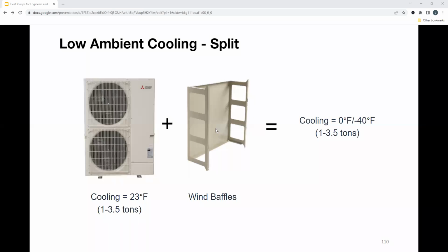And then quickly I just want to mention, I know Alex talked about this a little bit, the difference between low ambient cooling and low ambient heating. Just remember that when you are specifying this equipment, low ambient heating is the actual condenser, the outdoor units you select, whereas low ambient cooling is the addition of wind baffles and low ambient units, right? So if you are working on server rooms, we do have precise temperature control with these, with a little bit higher sensible heat ratios to basically produce that sensible load versus the latent load.